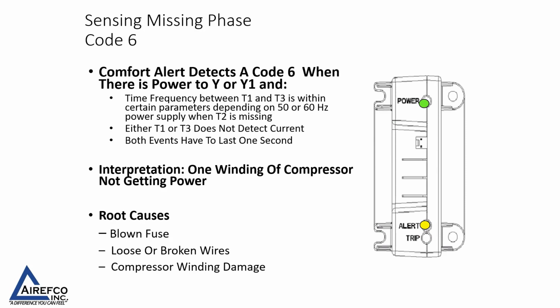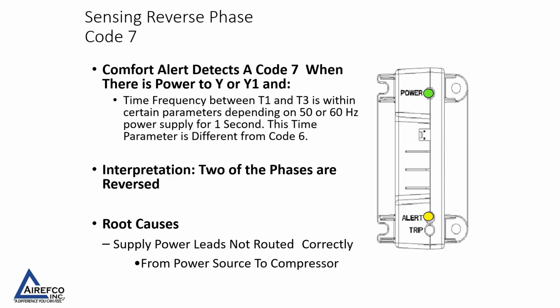A code 6 on the amber LED is sensing a missing phase. Since this device monitors all 3 phases of incoming power, it will detect when one winding of the compressor is not getting power. And so it gives you some root causes to look at why this may be happening. A code 7 flashing on the amber LED detects reverse phase on a 3-phase unit. This could happen by changes in the electrical panels at the job site, or by somebody moving electrical wires supplying voltage to the unit. So 2 of the 3 phases are reversed, and it gives you a root cause to look for to resolve the issue.